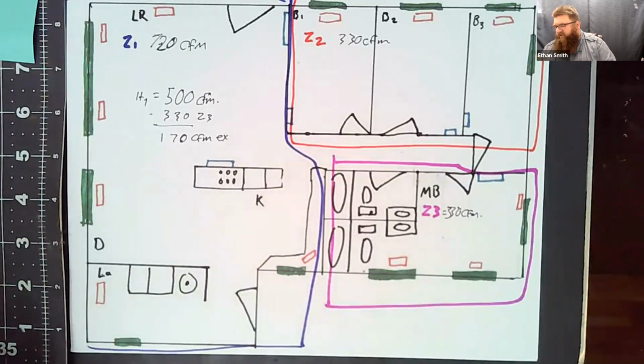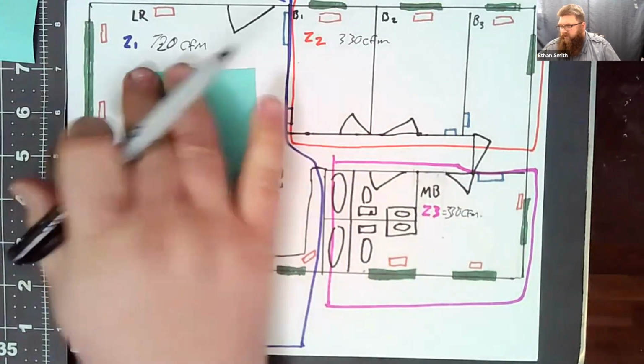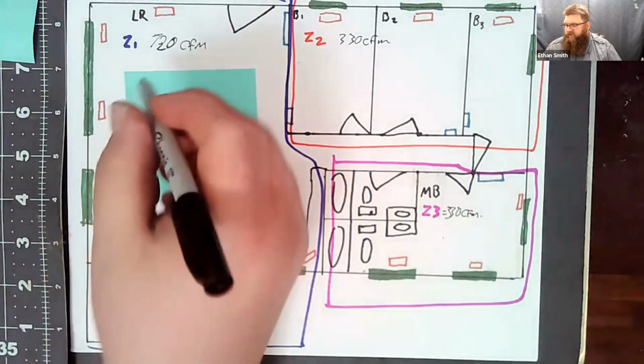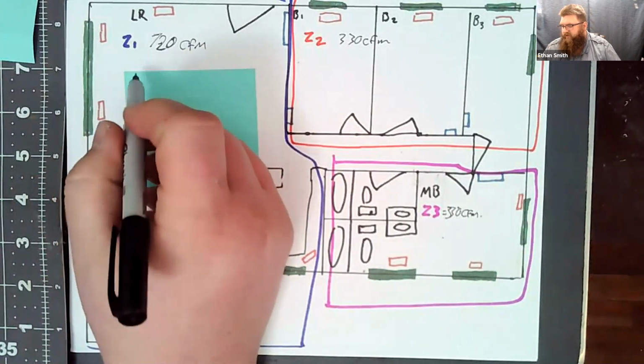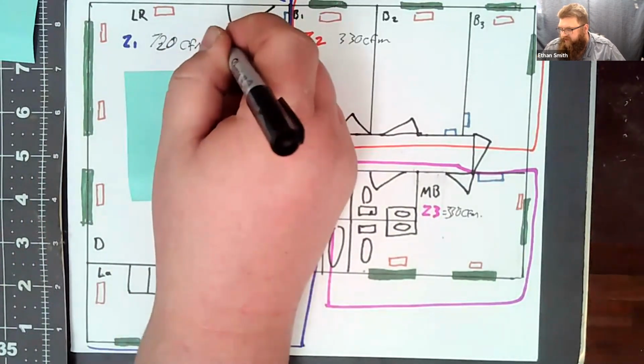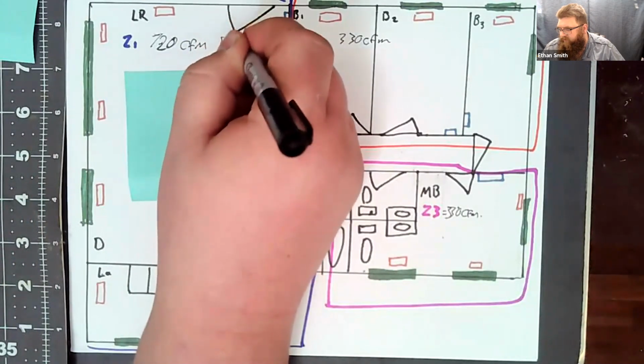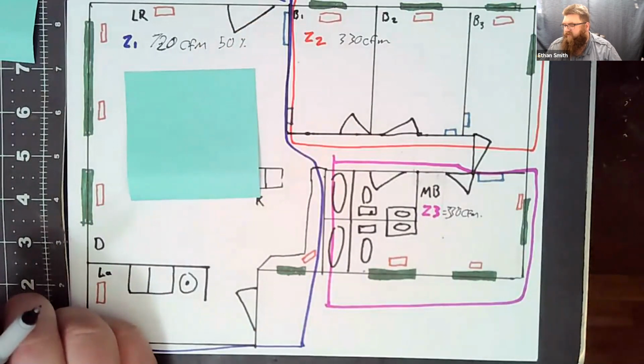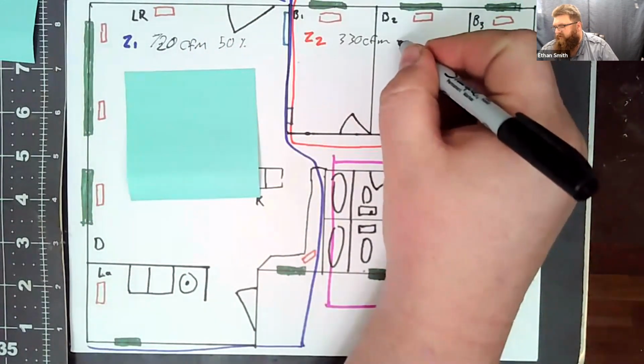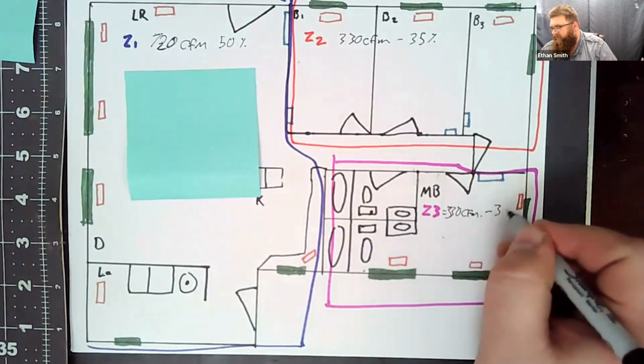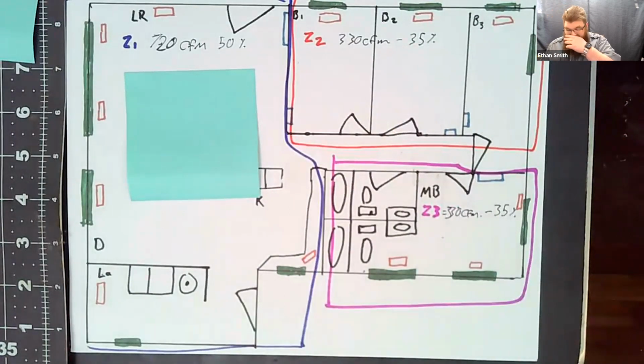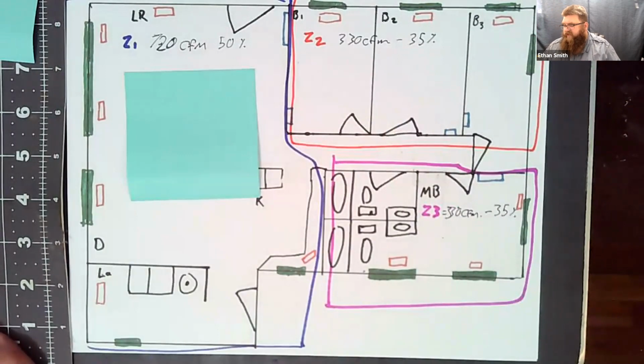So what we can do is something called intelligent relief. Where this comes into play is we can have a zoning system that calculates a load for each zone. So we can get an intelligent zoning system that knows that my zone 1 is capable of carrying, say, 50% of my system capacity. My zone 2 is capable of carrying roughly 35% of my system capacity, and my zone 3 is capable of carrying roughly 35% of my system capacity. Okay. So now my zoning system knows what size each zone is.